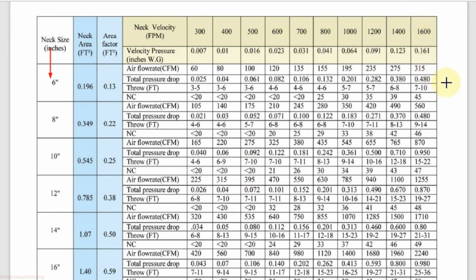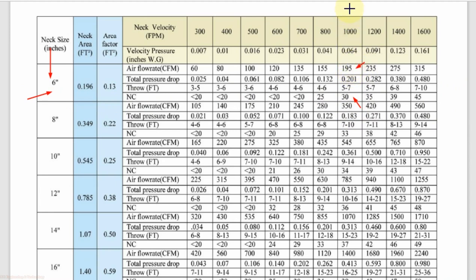But if your duct is designed at a higher velocity and you can provide that neck velocity, then you can first check the NC level. For example, for 6-inch neck size the NC level values are 25 and 30. If our NC level limit is 30, we will select that one. For this, the CFM value for 6-inch neck size is 195, but it requires 1000 FPM neck velocity. If we can provide 1000 FPM in our duct, then we can select the 6-inch neck size for 195 CFM.